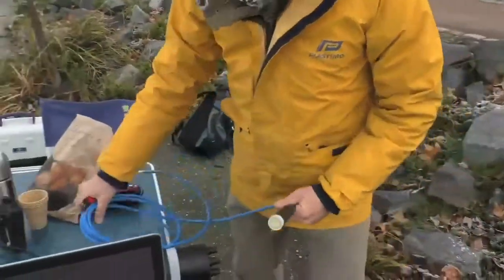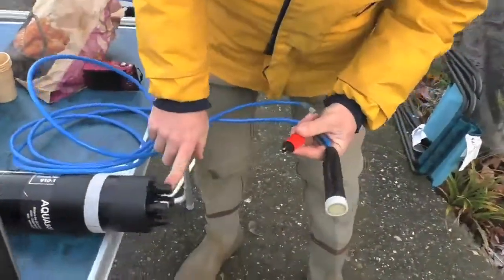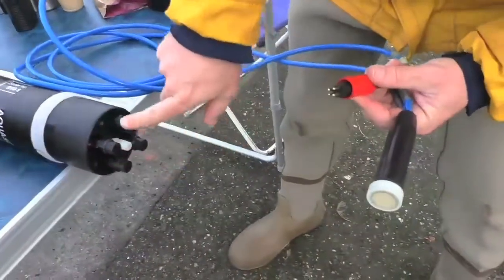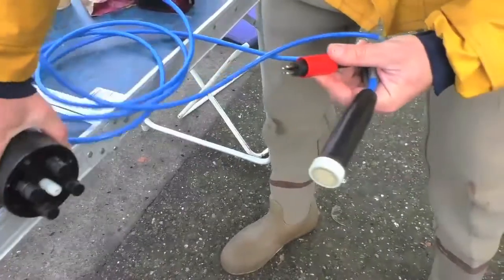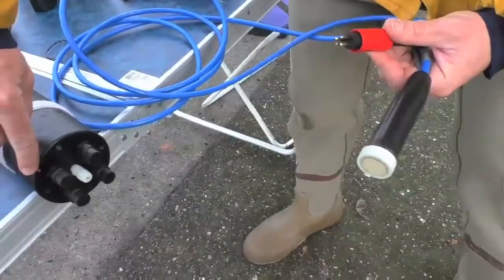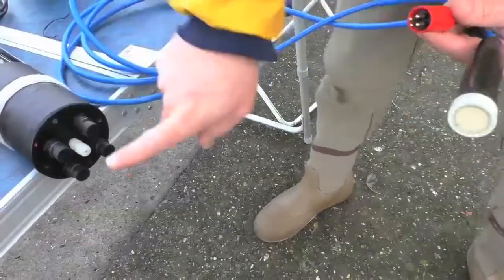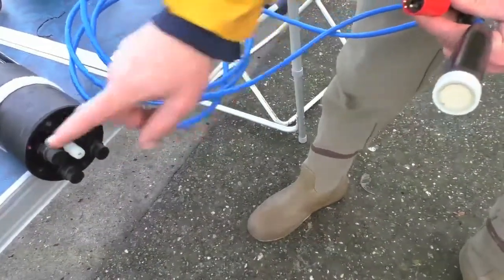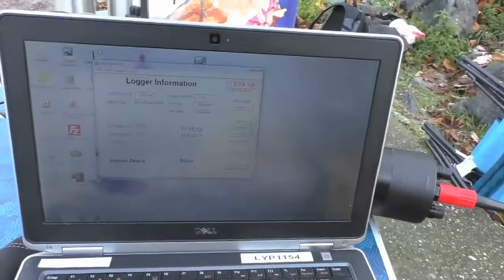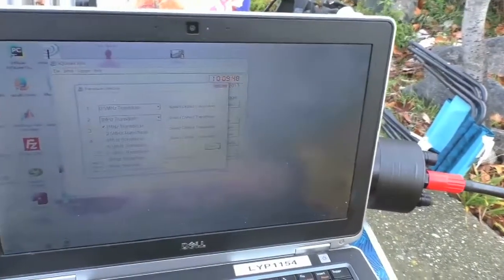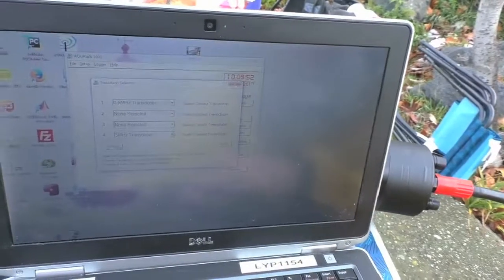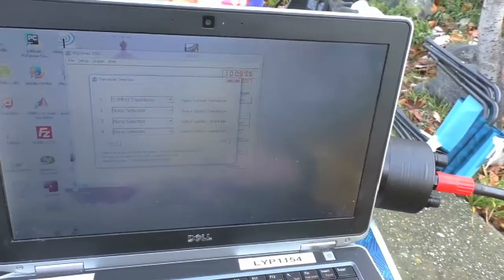Second check is to plug one transducer. There are 4 channels. Channel 1 is marked with a purple point. Then channel 2, 3, 4 are located clockwise. We click on Deploy to check whether the instrument is actually working. As we just plugged one transducer, we select the corresponding channel and the corresponding frequency and set the other channels to non-selected. Then click on Next.